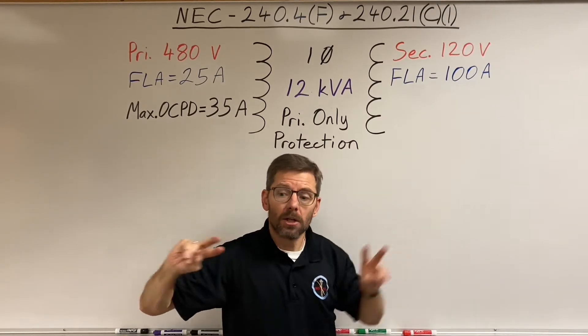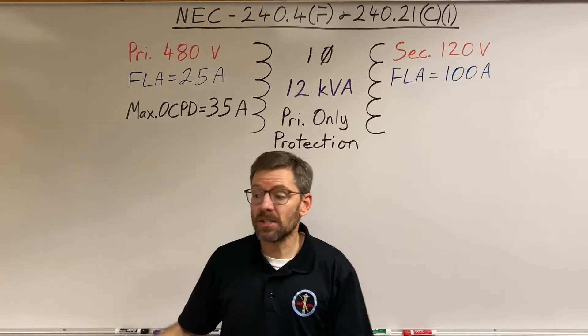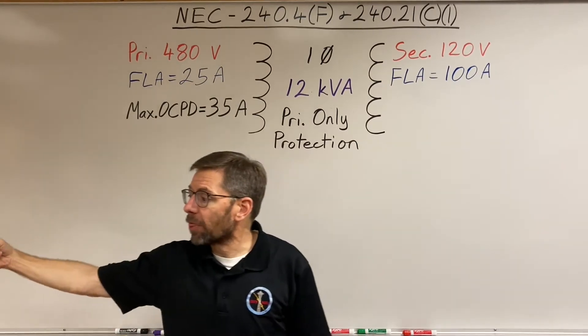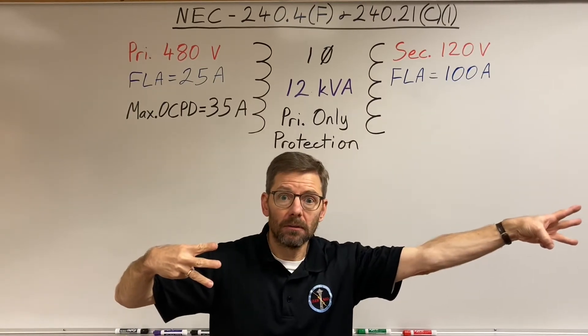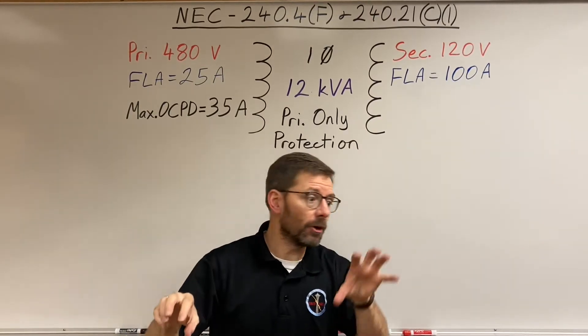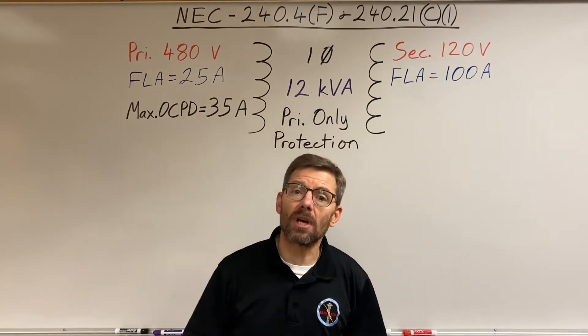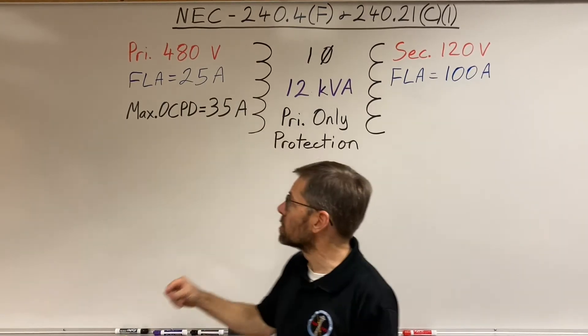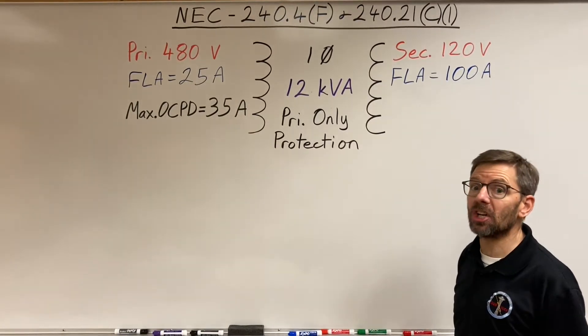No neutral, no third wire, just two in, two out. Or a three phase delta-delta with three wires coming in on the primary and three wires going out. That's the only two times I can use a primary overcurrent device to protect a secondary conductor.